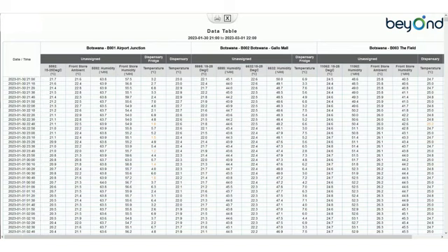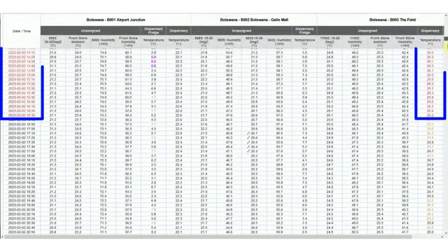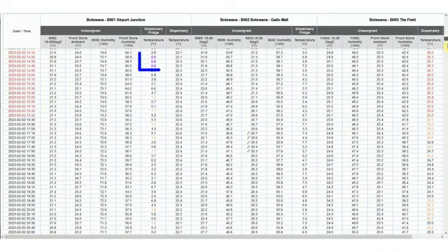All normal readings are entered on the report in black. Readings that indicate a warning, that is, a borderline condition, are entered in orange. Readings that indicate an alarm, that is, a critical condition, are entered in red. If any sensor is known to be faulty, data entries in the relevant cells are shown in purple. If any data entry has a wrench next to it, the Cold Cloud unit that generated the result was in test mode.